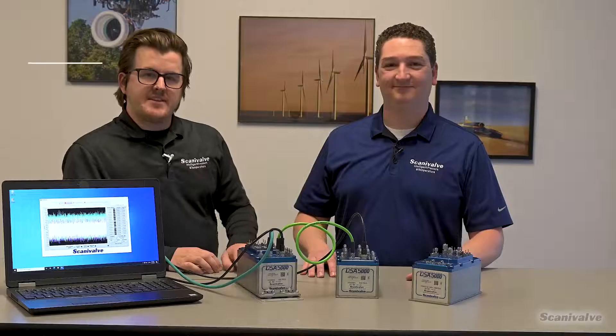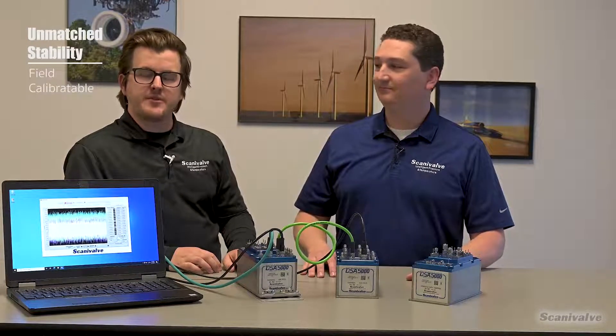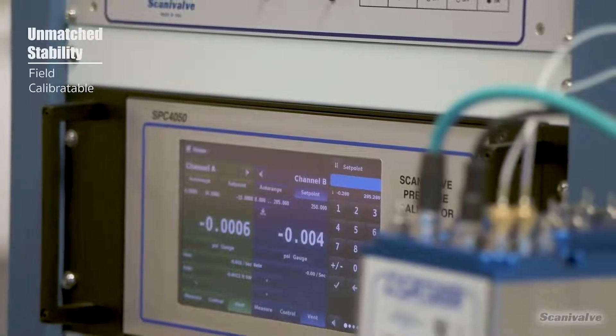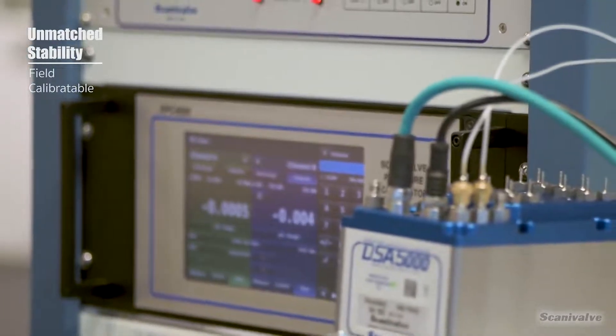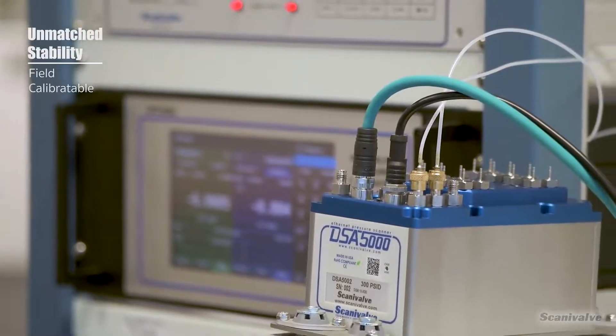The accuracy of the DSA 5000 can be maintained long-term in the field using Scanivalve's field calibration and validation software. Coupled with a Scanivalve calibration system, such as the SPC 4050, the DSA can be calibrated and validated in the field even without having to remove it from the test article.